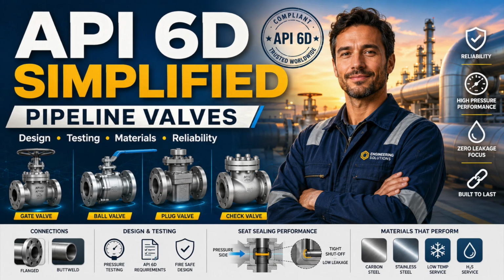The corrective action is to define the function clearly, define the hazard, define the pressure source, define the flow direction, define the required isolation, define the cavity behavior, define the bore, define the pigging need, define leakage expectations, define materials, define temperature, define sour service conditions, define actuator duty, define testing, define maintenance. Then ask the manufacturer to demonstrate how the proposed design meets that requirement. That is engineering. API 6D provides the structure, then the vendor provides the equipment, but you provide the intent. And when the intent is weak, the equipment can be compliant while the system remains wrong.